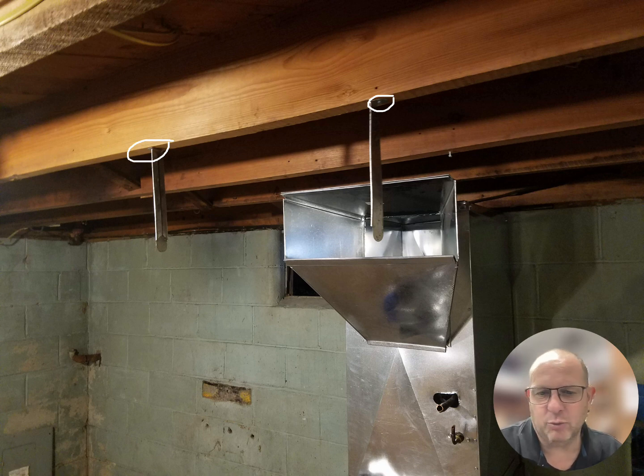A lot of people don't like to run their ductwork like that, because they're afraid of the vibration off of the unit being transferred into the joist, and then into the living environment of the individuals in there. Really haven't had an issue with that. If our furnace is vibrating that badly, then there's something else that we have to look at that's going to lead us to the problem of that vibration.